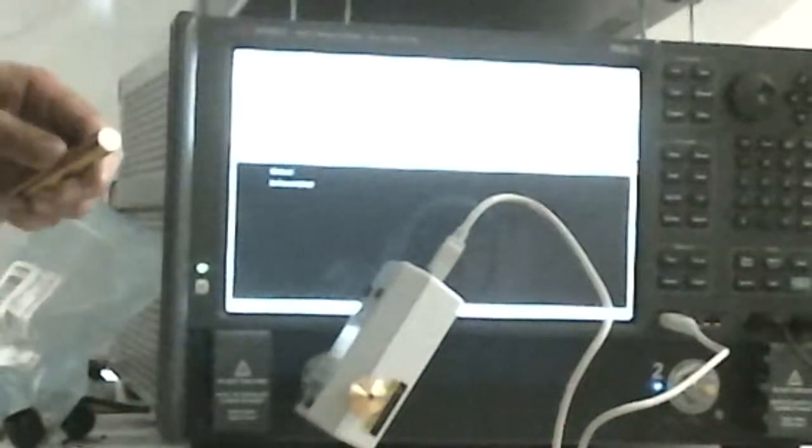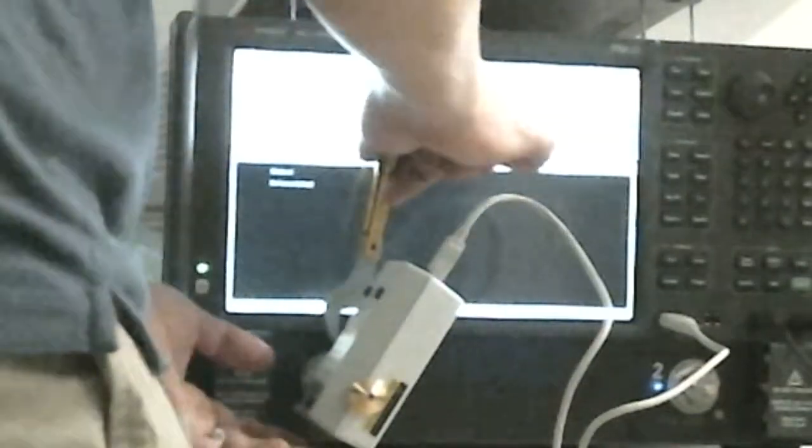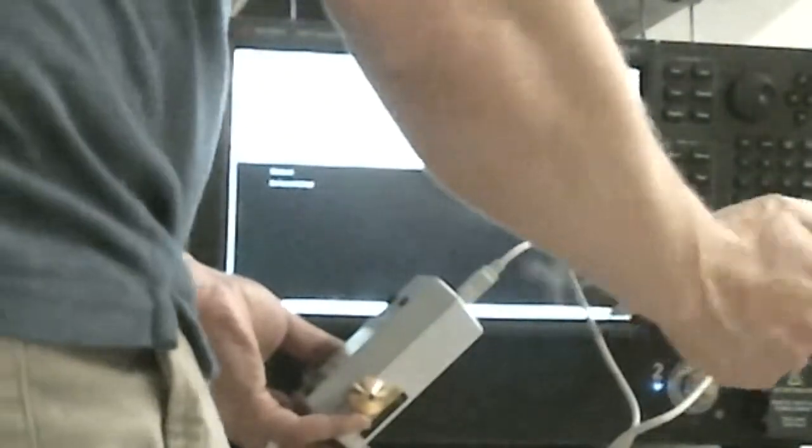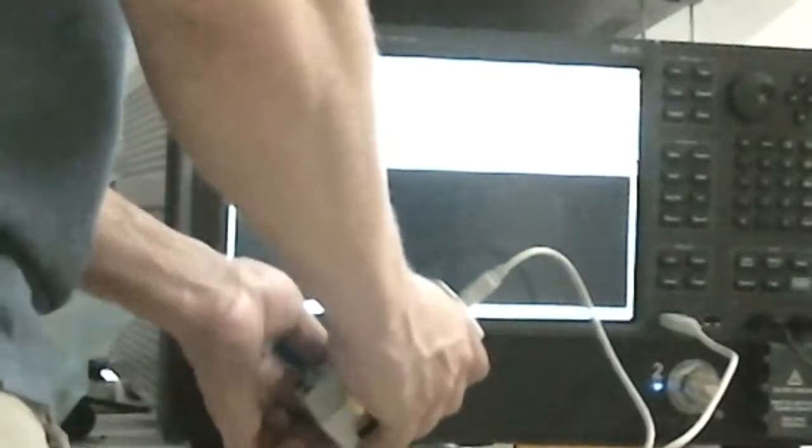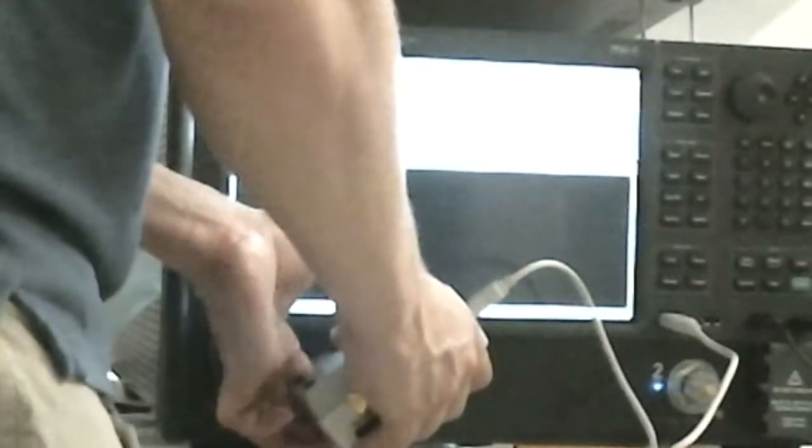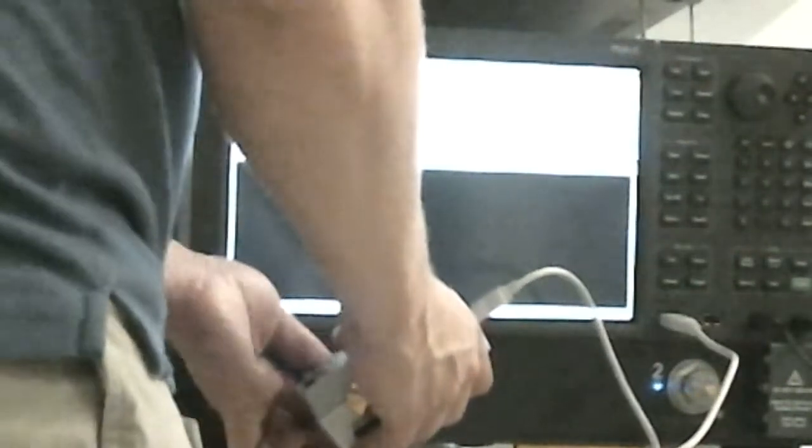So this can give you some level of confidence. It's not fully mistake-proof, but it gives you a really good way to verify some of the issues before you go through the entire calibration. Because if you've gone through the mechanical calibration and you make that mistake, you don't realize it until the very end of the calibration, right? Okay.